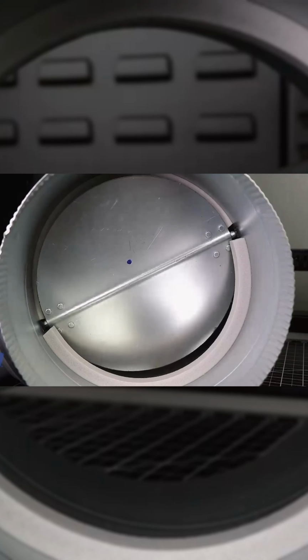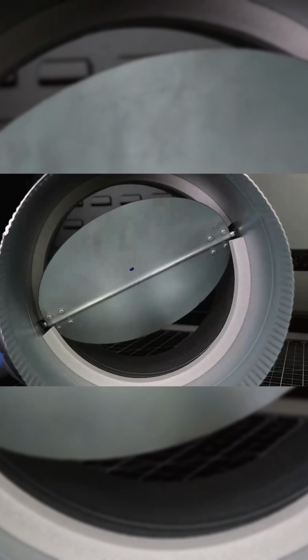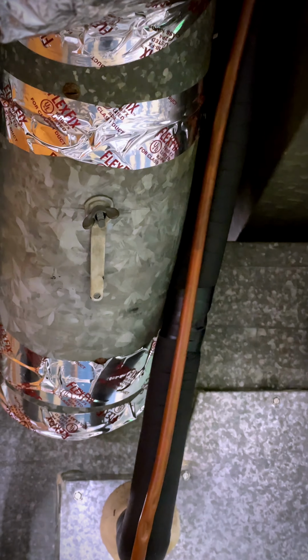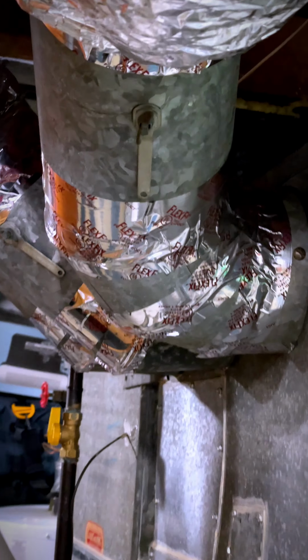Side note, you might have noticed that my duct insulation stops about 2 feet before we hit the plenum on every one of these runs. And that's for a good reason. These little levers all control the damper doors. You'll use these later in the event that you have your ducts cleaned, because you need them fully open for that. But also you'll use these to make air balance adjustments, or at least that's what I'm going to do, because that increases efficiency as well as the evenness of your climate control distribution throughout the structure. It's going to make it more comfortable and cheaper to maintain.